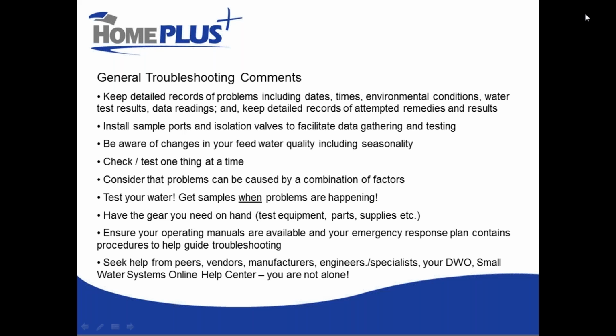Also on the topic of being prepared, ensure you have operating manuals available. Lots of them have very good troubleshooting guides in them that can help you navigate through the troubleshooting procedures for each specific piece of equipment in your system. Certainly have your emergency response plans available, and make sure that those contain some guides to common troubleshooting procedures, especially if you have a lot of turnover or you have a substitute operator stepping in who's less familiar with your equipment. Having that information available to them goes a long way to getting a quick resolution. They know where to go to get some extra help.